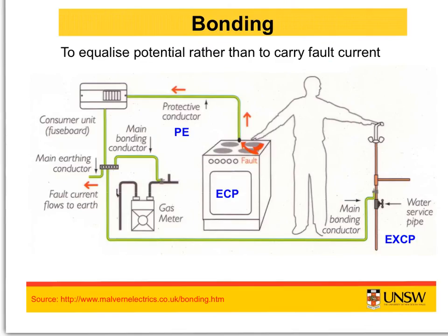So apart from earthing, we also have something which is called bonding. Bonding is a process of establishing a required degree of electrical continuity between various conducting surfaces. In contrast, earthing is an establishment of an electrical conductive path between a circuit and some reference structure. So earthing is actually a conducting path or choosing a reference. The main purpose of bonding is to equalize the potential rather than to carry the fault currents, whereas the main purpose of earthing is to carry the fault currents. So the bonding conductor should be very short and direct wherever possible.